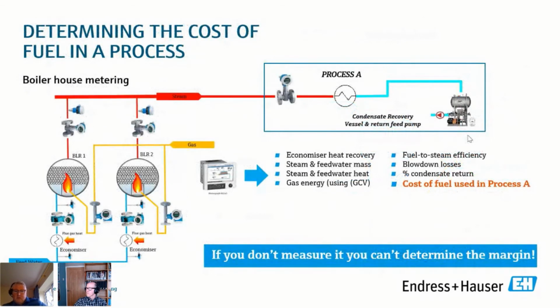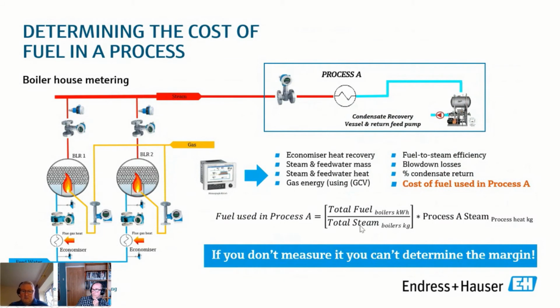And there was one other parameter that we didn't touch on then, and it's looking at the cost of fuel in the process. So with obviously increasing gas prices, the profitability of products in some areas because of steam heat now costing much more can be calculated quite accurately. If you know the fuel economy, if you instrument the boiler and we get to the measurements we've just looked at, then as long as we're measuring steam in that process, then it's a very simple calculation.